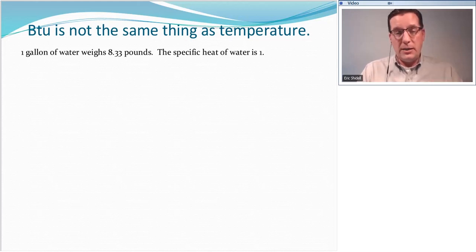When we're troubleshooting heating systems, we need to look for where is the heat energy moving, and that is the important part of our heating system. Very frequently, when technicians run into trouble around diagnosing heating systems, the reason why goes something like this. They say, hey, it's really hot, therefore I shouldn't be having a problem. So the problem isn't the fact that it is or isn't hot. The problem is heat isn't moving in the right quantities. So just because something is hot doesn't necessarily mean it's an effective heating system. And so to illustrate that, I want to talk a little bit more about this whole idea of a BTU and the 1 degree per 1 pound and those kinds of things. Remember, heat is a unit of energy.